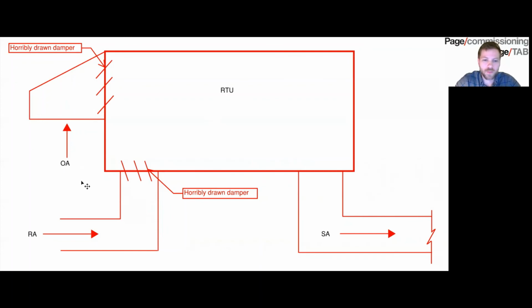But again, I always try and find ways to use the pitot tube because it is your most accurate method of reading airflow in the field. And so I was just trying to give you some ways to think outside the box and get your most accurate calibration of your outside air, because that affects your building pressurization.